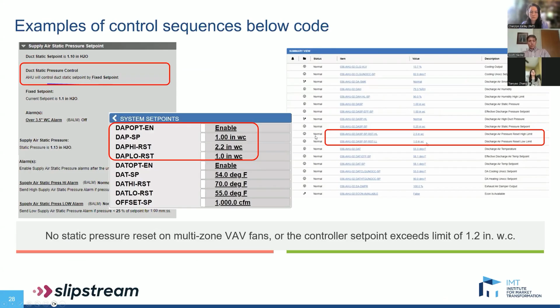And here we have some example screenshots of BAS settings that reflect a control sequence that's below code. To the left here, we have a setting showing how the static pressure control is on a fixed set point rather than on a reset control. And to the right here, these two graphs show the maximum limit exceeding the 1.2 inches that's required by code.